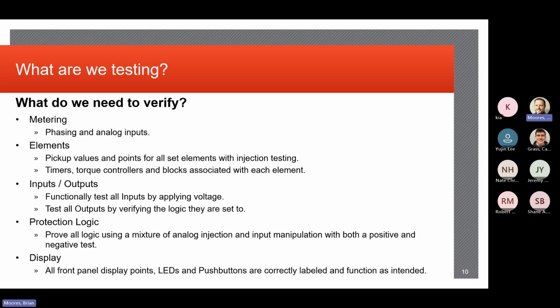Maybe there's a physical problem, maybe there's a wiring problem. So we want to check those things. And we want to check all the elemental pickups. We talked about distance relaying last week. Well, there's the mho circles. We want to make sure that everything is working inside the circle and doesn't work outside the circle, the impedance related settings. Overcurrents, voltages, they're going to have set points. You're going to have an instantaneous overcurrent of 16 amps or whatever the application calls for. We want to make sure it picks up after 16 amps and not before. Voltage under, over, all of the things that are set. And you would have to go through and make sure you're checking all those relay settings to ensure you're figuring out what's actually turned on.